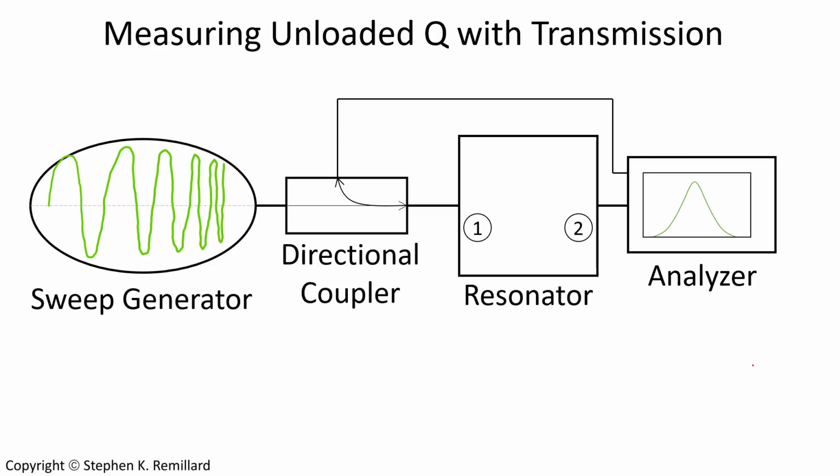Today I'm going to talk to you about how to measure the unloaded quality factor Q of a microwave resonator. Theoretically, it is the stored energy divided by the dissipated power, U being stored energy, omega is angular frequency. Because it's inversely proportional to the dissipated power, it makes sense then to say that it is a measure of the quality: small dissipated power, high value.